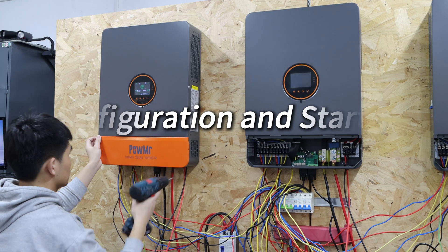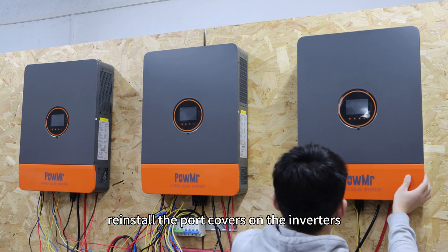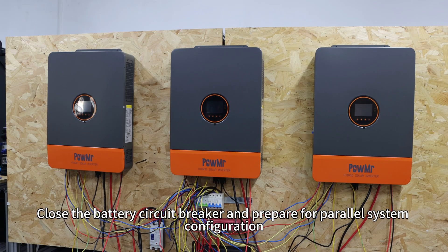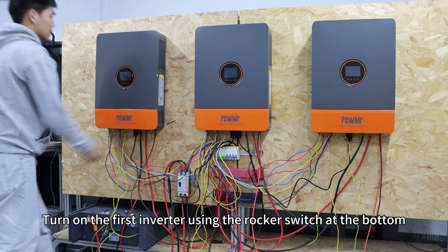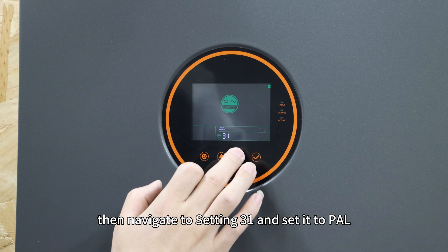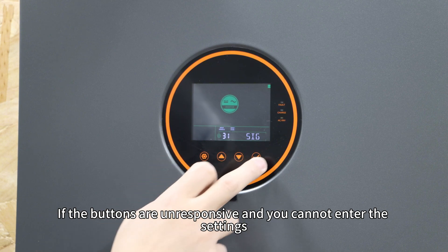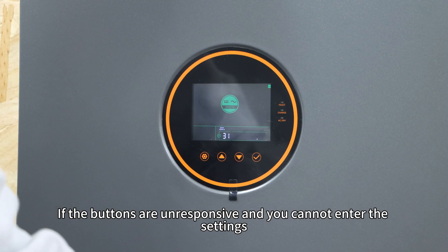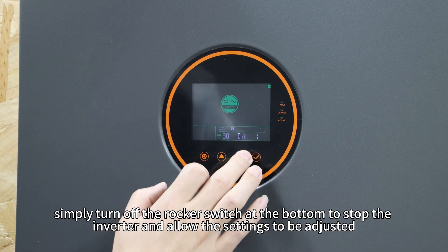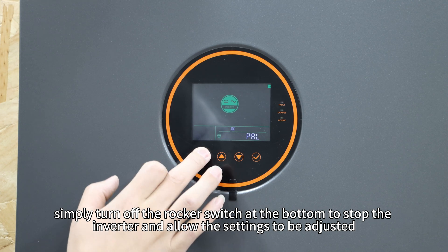Configuration and start-up. After verifying that all connections are secure and correct, reinstall the port covers on the inverters, close the battery circuit breaker, and prepare for parallel system configuration. Turn on the first inverter using the rocker switch at the bottom, then navigate to setting 31 and set it to PAL. If the buttons are unresponsive and you cannot enter the settings, the inverter may already be in inverter mode. In this case, simply turn off the rocker switch to stop the inverter and allow the settings to be adjusted.